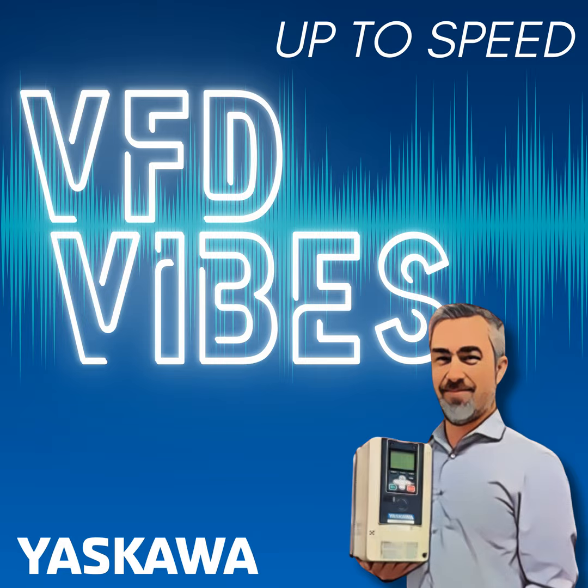If someone were installing a drive tomorrow, from all this discussion, what would be your key takeaways, or the most important things you'd want them to think about? Well, the first thing is to know what kind of power supply you have. What does your power distribution system look like? You're going to hook this drive up to a 3-phase power line. It's very helpful for you and for us to know, is that grounded back at the service entrance? If it's not grounded, is there a reason that it's not grounded? It could be that it's supposed to be grounded, it just simply isn't. If you know what kind of power system you're connected to, then we can give you much better advice. The drive may work just fine. Hook it to the motor and be done.